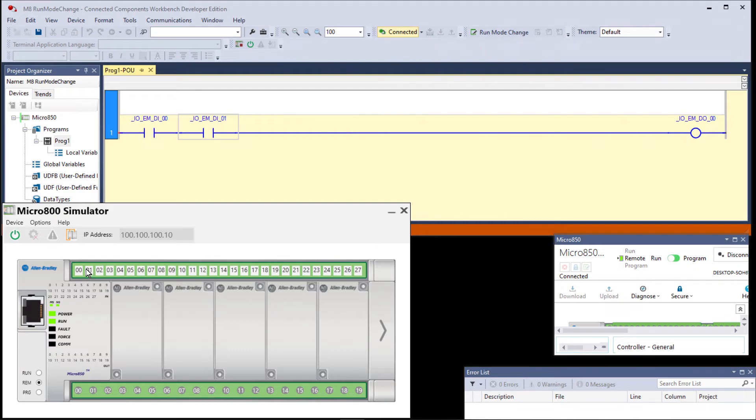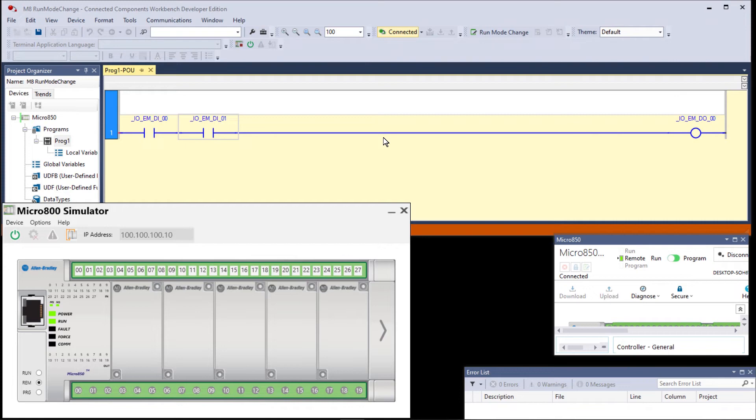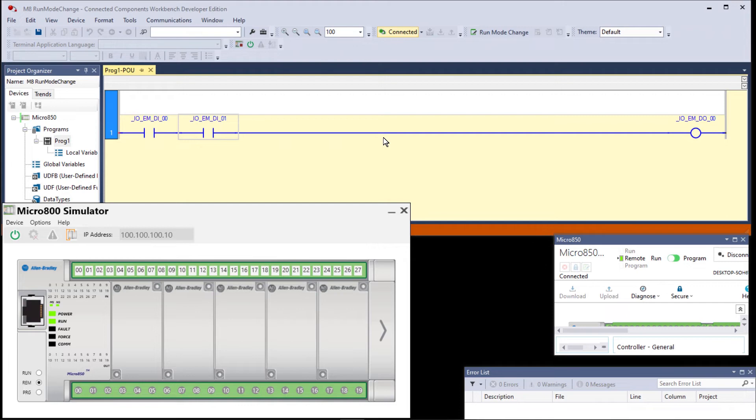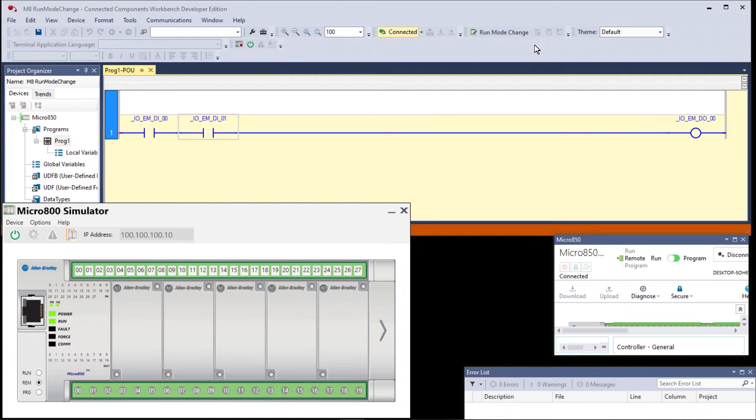All done. That's how easy online edits are. In the manual we had several questions. The first one was before we were going to test—it said mouse over these two choices that are now active. These two options became active because you clicked on run mode change. Your changes outside the running program—CCW likes the syntax. So what is the next step? What are your choices and what do they imply? Your choices are to test or cancel. If you choose test, then it's going to allow you to test your logic live running with your process. If you pick cancel edits or discard unaccepted changes—cancel edit same thing—if you click on that then it's going to eliminate any changes that you made.